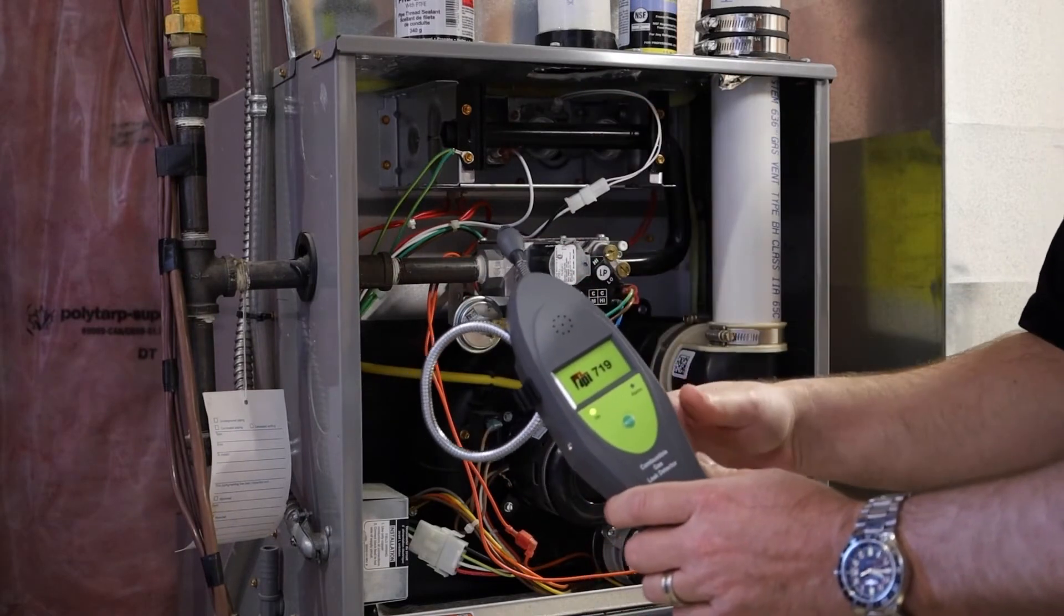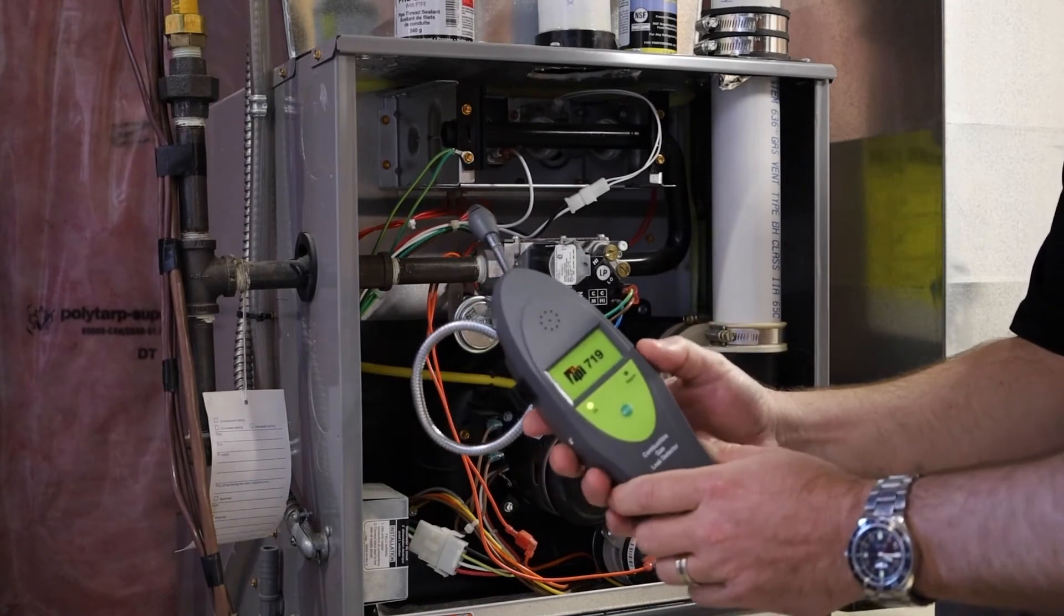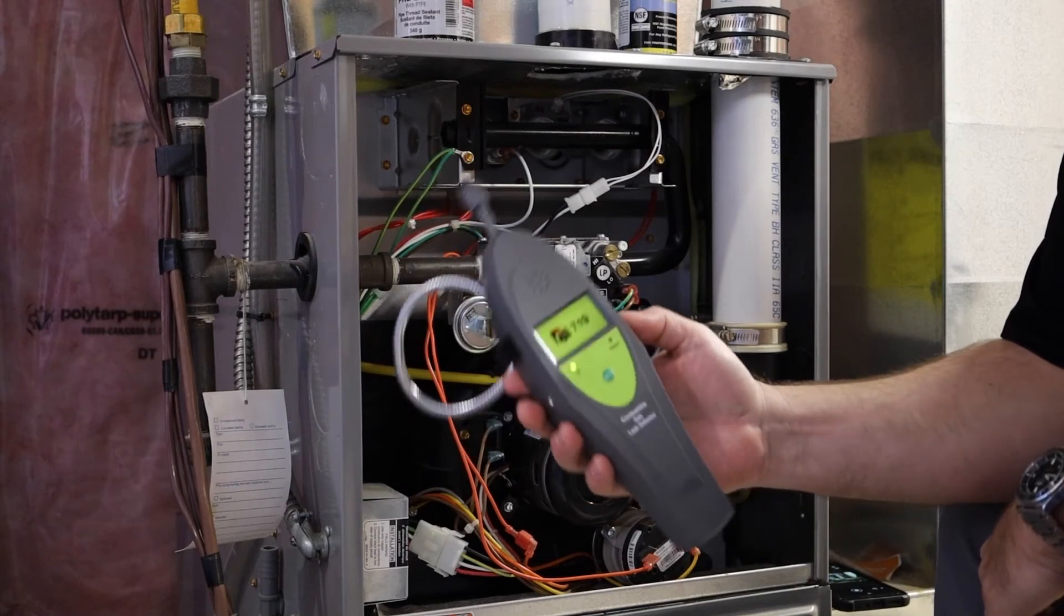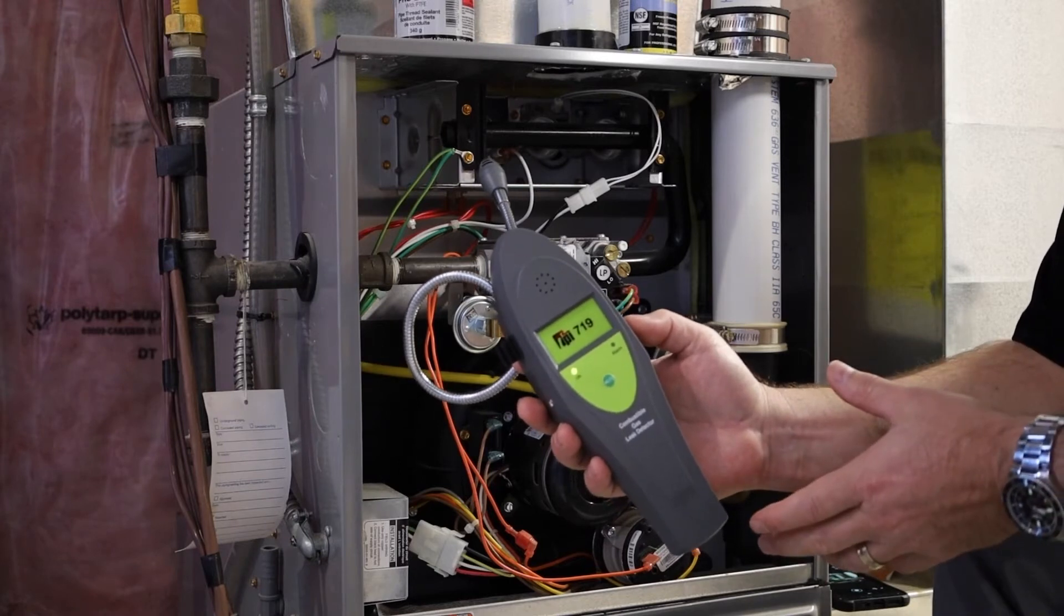Again working with fresh pipe dope you can do the same thing. Hold it above the jar of your pipe dope, zero it out and continue looking for your leaks. That's the 719 combustible leak detector. Again we'll do all your combustible gases.